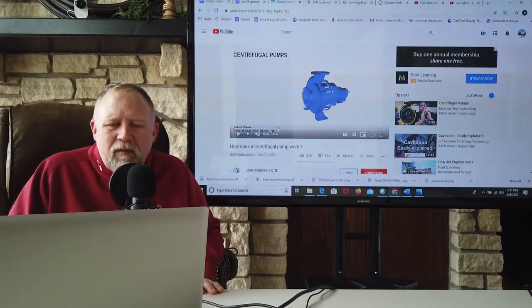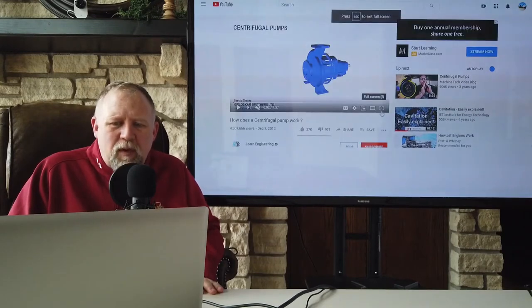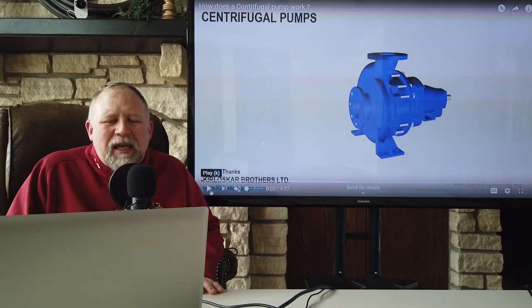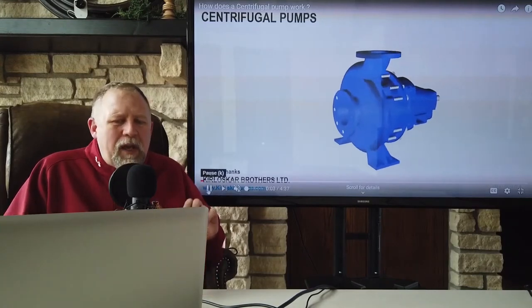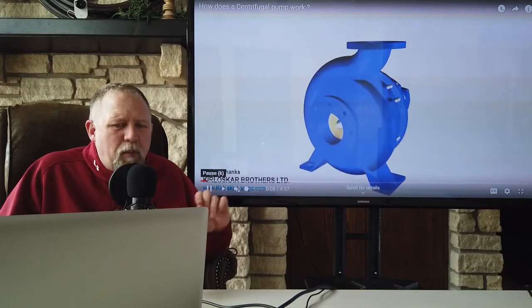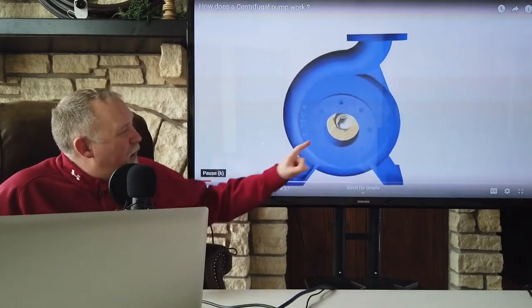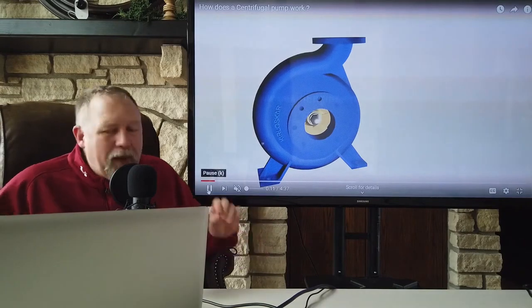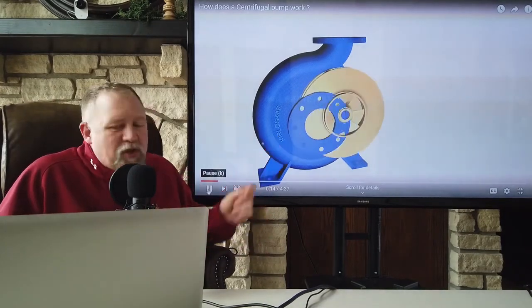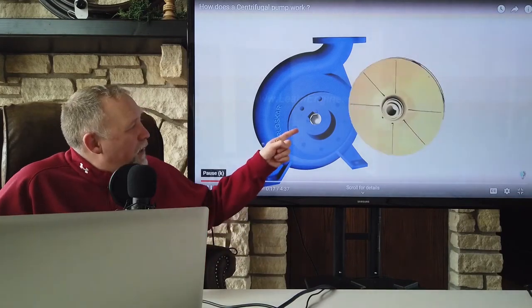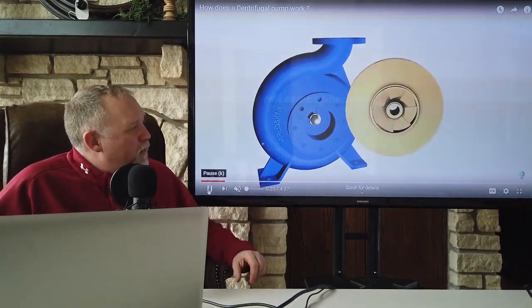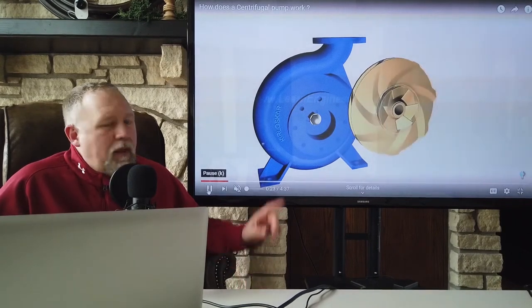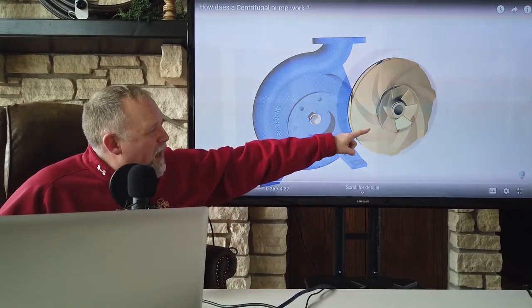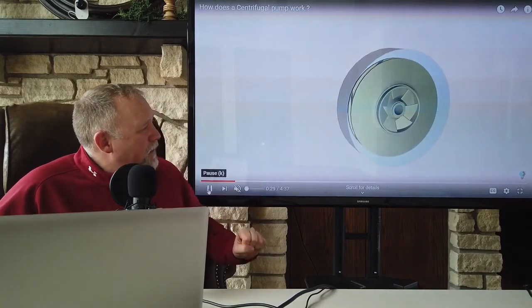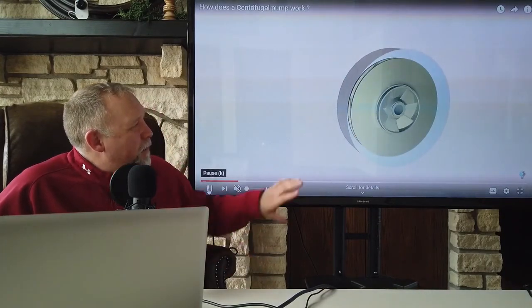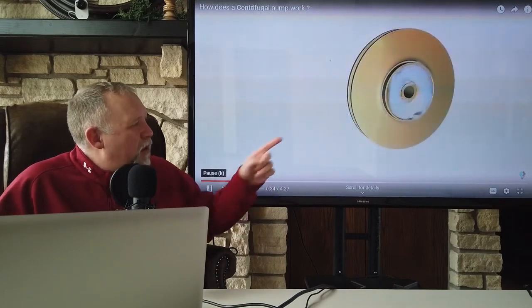I've got a video here that I found. Okay, we'll just take a quick look at this. Cavitation is when bubbles start to form at the low pressure point. The low pressure point on a centrifugal pump is going to be here at the inlet. A bubble will form because that pressure is getting too low. There's the impeller to make water flow through the pump, right? It's going to spin round and round, and you see those impeller vanes here in just a second.